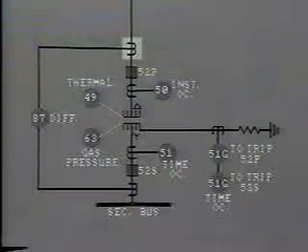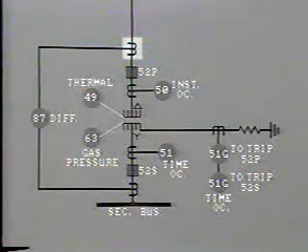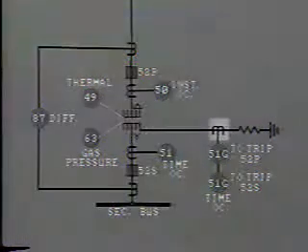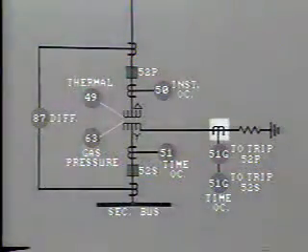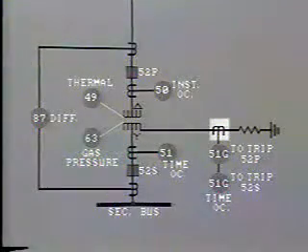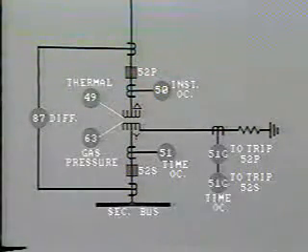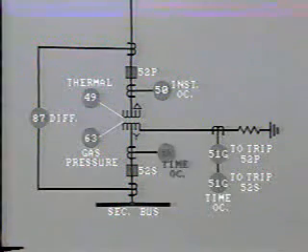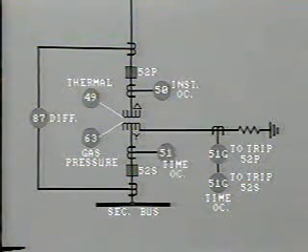This is a commonly used symbol for a CT, but please make sure you are familiar with your own company standards. This CT is installed in the neutral to ground connection, measuring ground current. It feeds time overcurrent relays, 51G. Another time overcurrent relay, 51, is installed on the secondary output before the breaker.